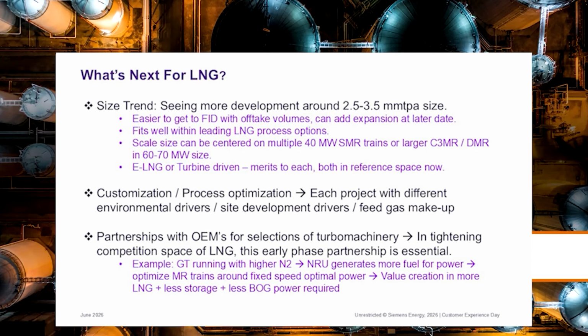And this is also sort of the new days of LNG, where you go back and look at Turbomachinery Symposium papers, which I've done, and very well written by experts in the industry. But when they were talking about LNG, the technology has changed so much in the last really 10 years or 5 years, where we see references in larger horsepower class for variable frequency drives. And that's sort of the key enabling technology that we needed to get to where we could do motor-driven LNG. Because we had motors and we had generators, basically a motor design, way over 100 megawatts, but we needed those VFDs to be able to give us references.